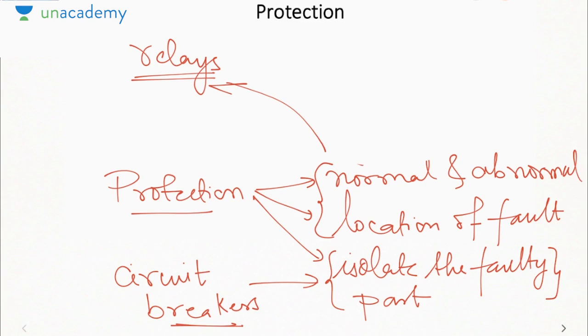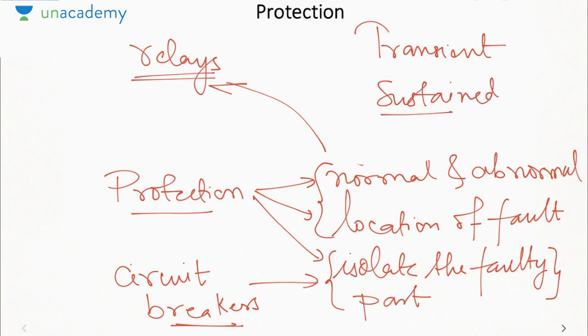Okay. And based on the time, faults are divided into two categories. One is your transient, other is your sustained. Now, as I told you, transient fault, it is something like inrush current, which persists only for a short duration. Sustained fault is which exists for a longer duration. So obviously sustained faults are more dangerous as compared to transient, because they will exist for a long duration in the system.